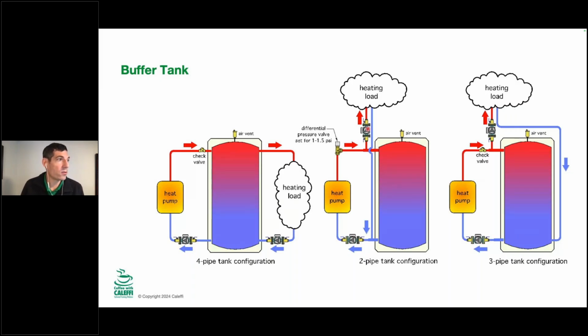Until we start to lose some zones as they come up to temperature, and then some of those GPM start to curl off the heat pump and heat up this tank. So we start to charge the battery. Then the heat pump turns off. If this is up to 140 degrees and one more zone comes back on here, we can actually pull flow from the right to the left to go out and heat up the building. So water can be going both directions through this span of pipe right here.